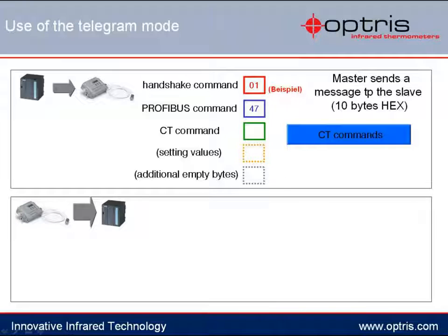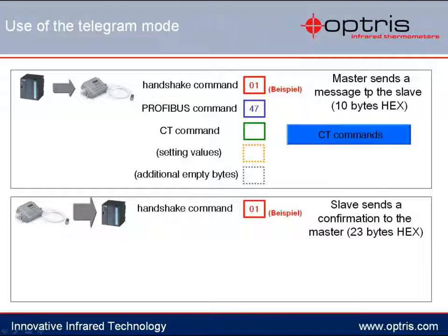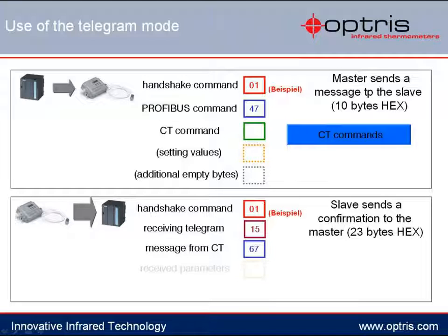The temperature sensor will reply with an answer telegram after receiving the telegram. This answer contains 23 bytes. The first byte returns our so-called handshake byte. The second byte follows with the value 15, indicating that a telegram has been received. The third byte is the answer byte from the temperature sensor, always the value 67. Afterwards, either the answer values from the sensor will follow if a request was sent, or the changed values will be received if new settings were requested. The missing bytes to reach 23 bytes will be filled with zeros.